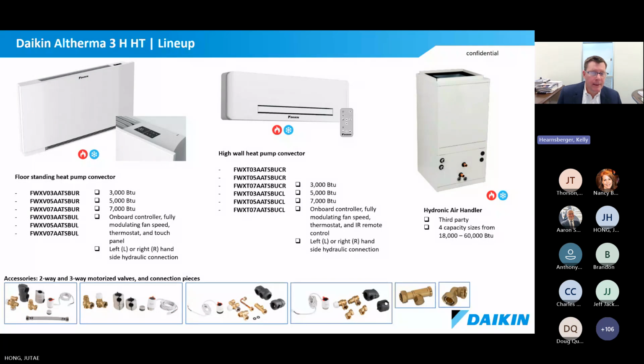Now, a little bit about the air movement capability. We've got, as I said, these premier convectors. We call them convectors, just call them air handlers, but they're really slim, very sleek profile. Even the high wall unit is about half of the size of the cassette that you'd see in a mini split. Pretty low profile, easy to work with. We also have isolation valves, depending on how you plumb these things. You can run these all in parallel. And then, of course, you don't need to pump the water through the coil to get to the next unit if you're in one circuit.